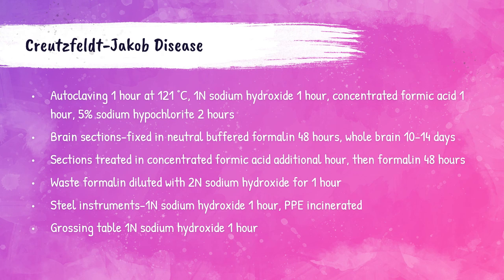If using steel instruments with brain tissue, they need to be processed in 1 normal sodium hydroxide for one hour, and any PPE used must be incinerated. The grossing table used for this tissue should be cleaned with 1 normal sodium hydroxide for one hour. All these measures will help protect the histology laboratory worker from CJD prions.